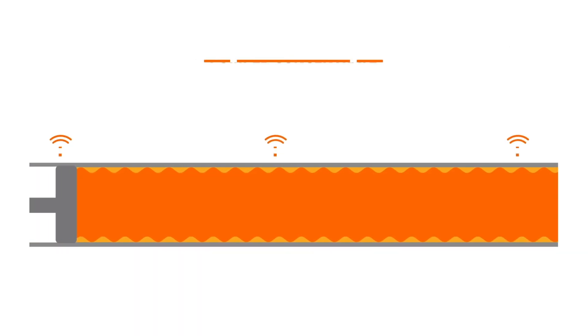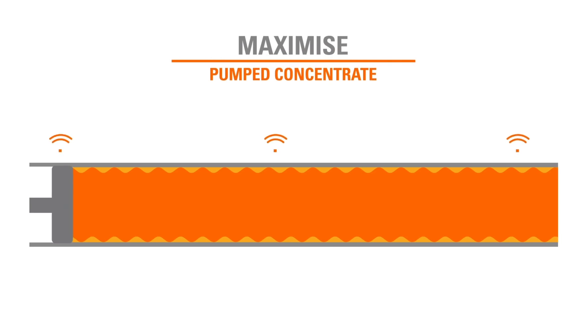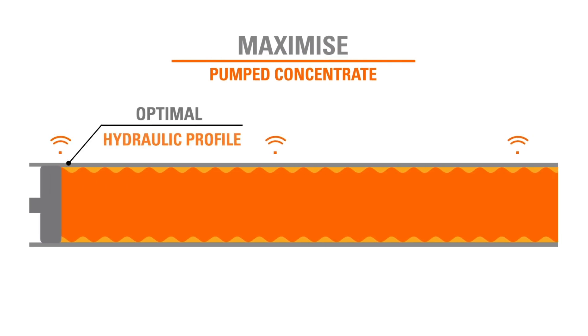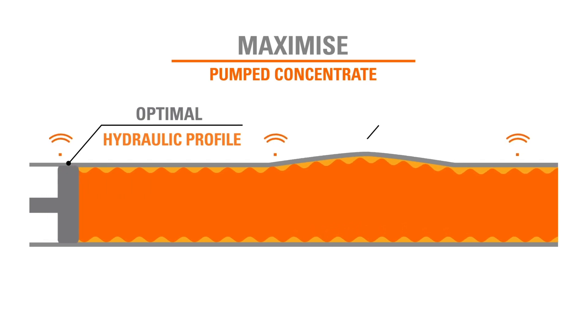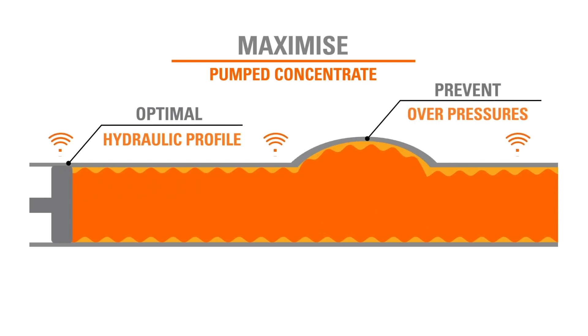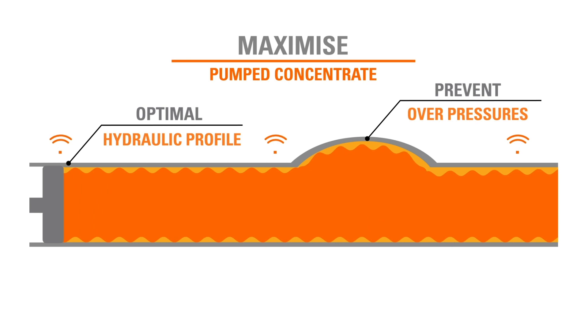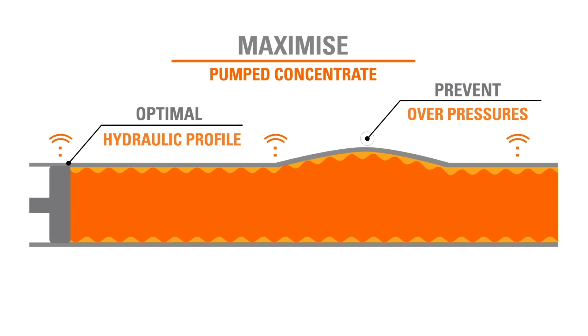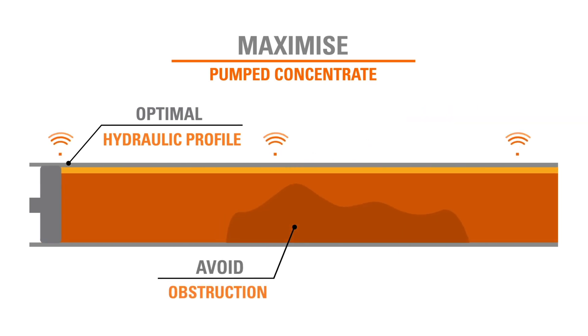Ore duct. We maximize pumped concentrate ore flow while keeping the ore duct water level within acceptable parameters, preventing excessive pressure that might cause early wear and tear, and avoiding solid sedimentation that obstructs pulp movement, which might cause full duct obstruction.